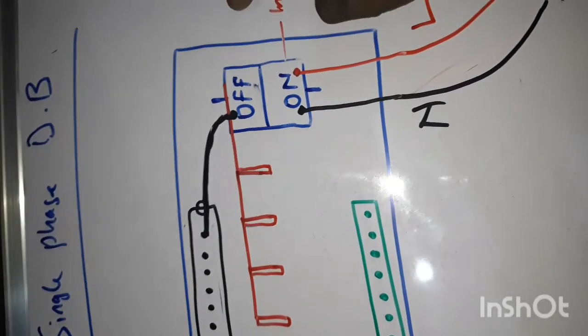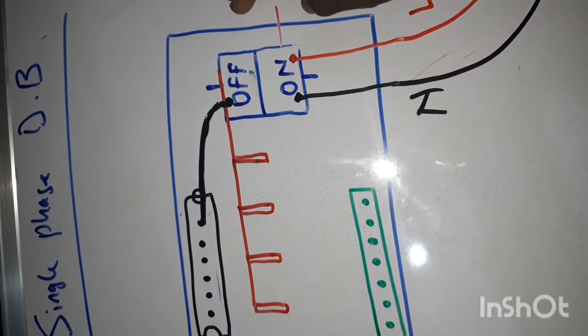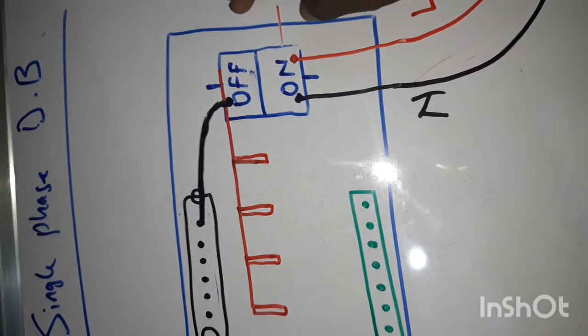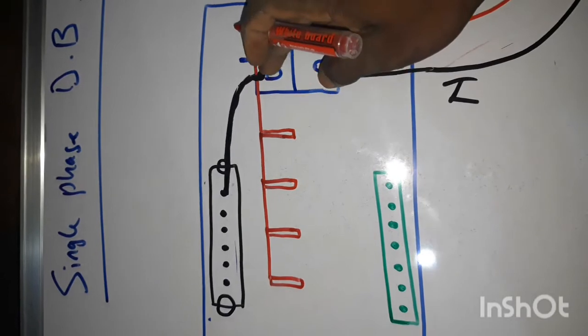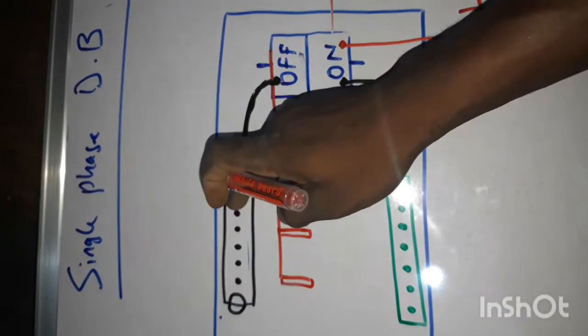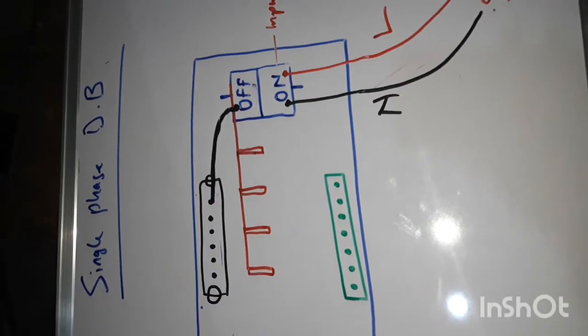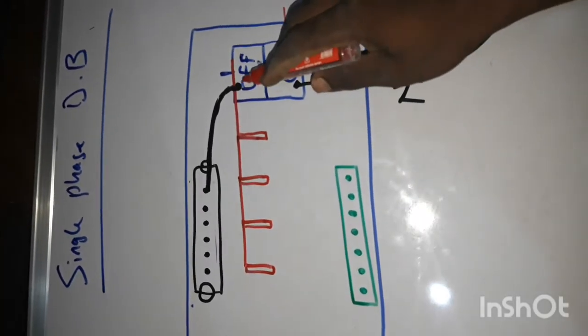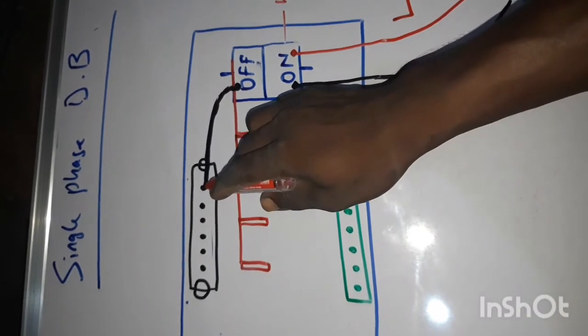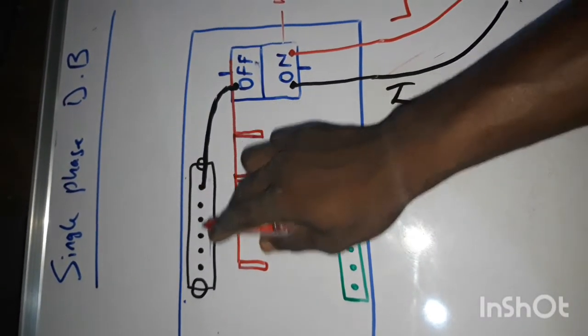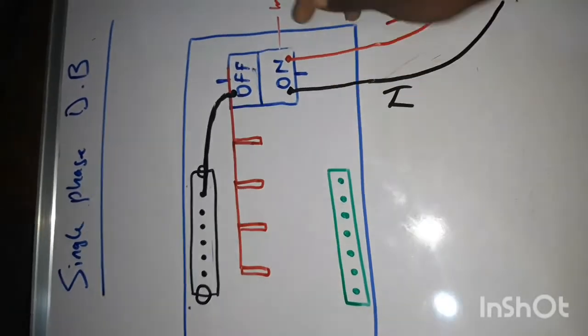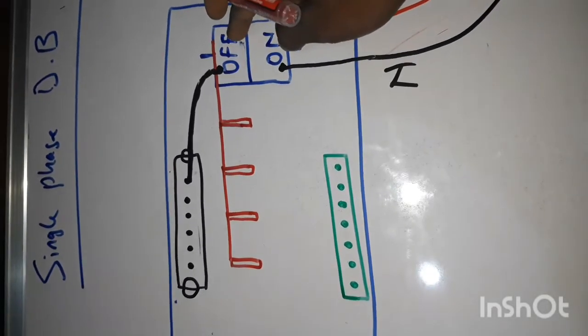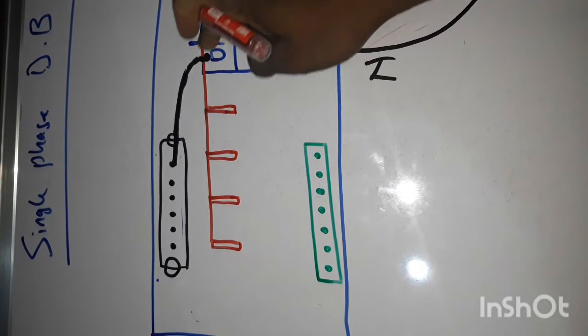If you look closely on the main circuit breaker, you can see that a wire has already been looped for you from the output of the circuit breaker to the neutral bar. So the neutral part of the output has been linked by the manufacturer. They've linked it to the neutral bar already. The output of the live part has also been linked to the bus bar. You don't need to do that one. That one has been done.